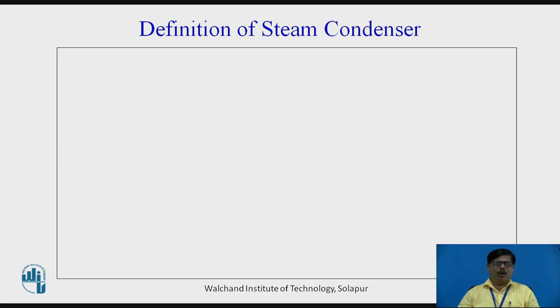In case of turbine or steam engine, if you want to let out the steam after expansion in the engine or turbine to the atmosphere, then we can expand the steam maximum up to atmospheric pressure theoretically, or practically speaking, the pressure of steam should be higher than atmospheric pressure so that it can come out. However, if you want to expand the steam below atmospheric pressure, then we need some closed vessel in which we can expand the steam below atmospheric pressure, that is vacuum pressure, which is called as the steam condenser.